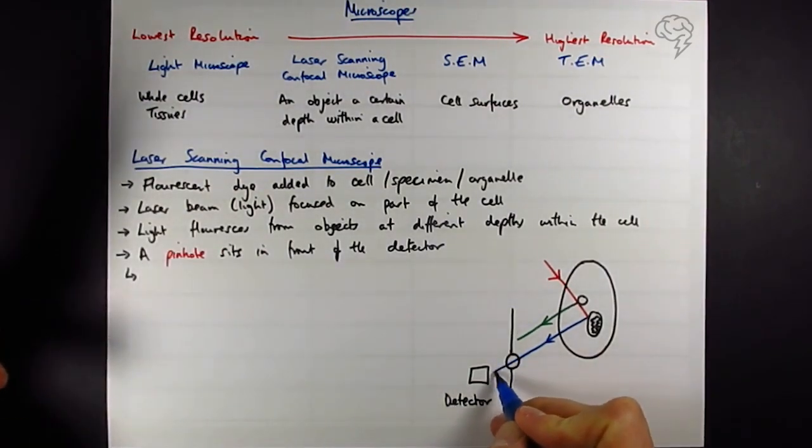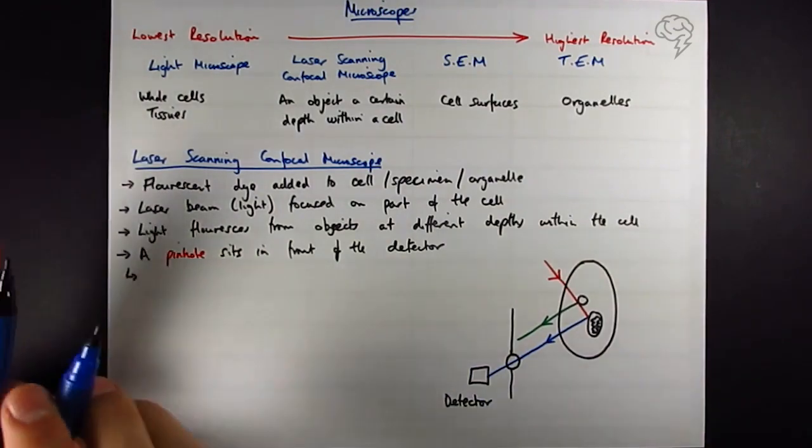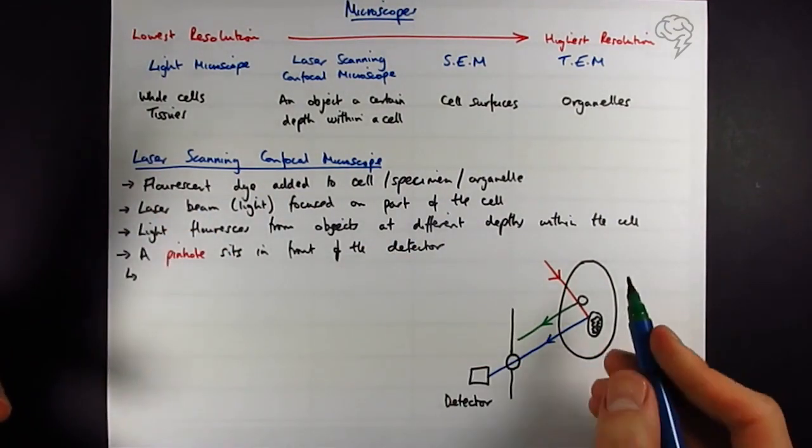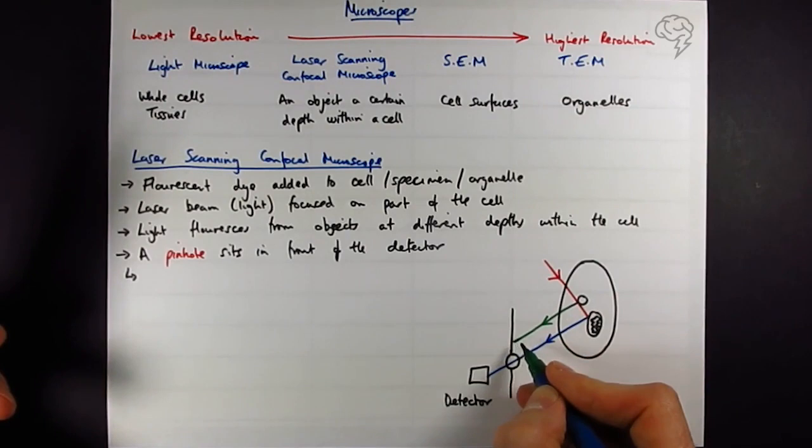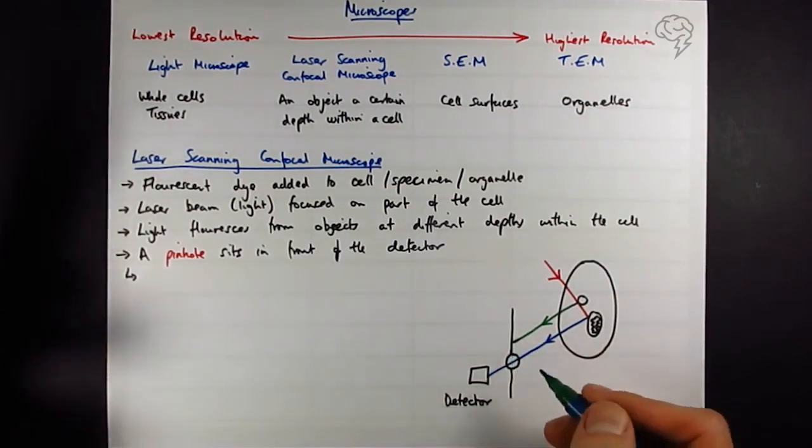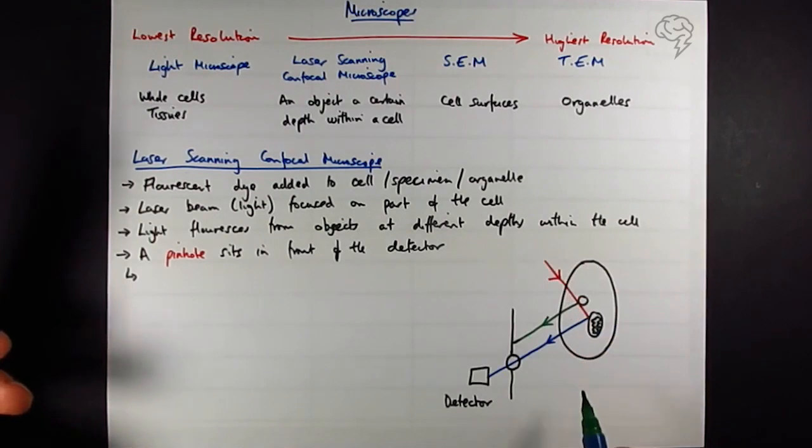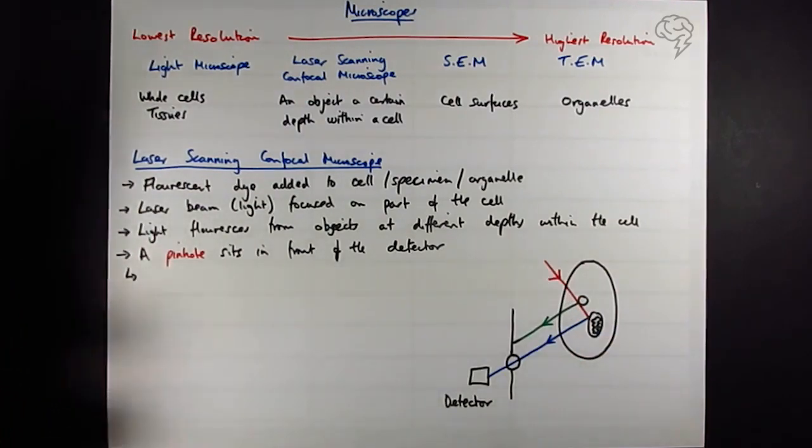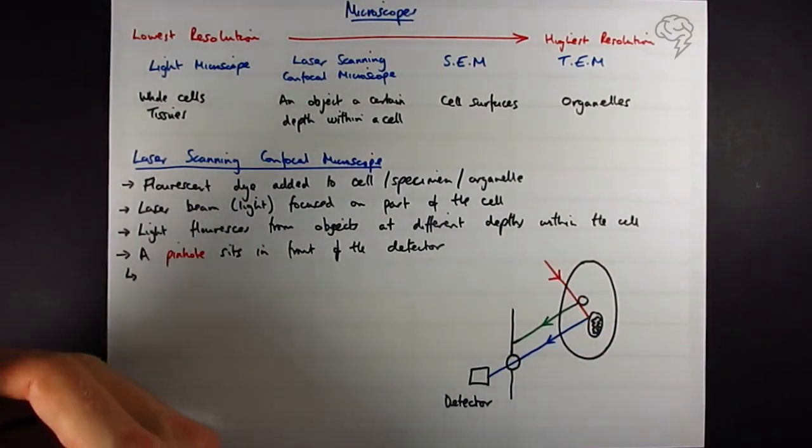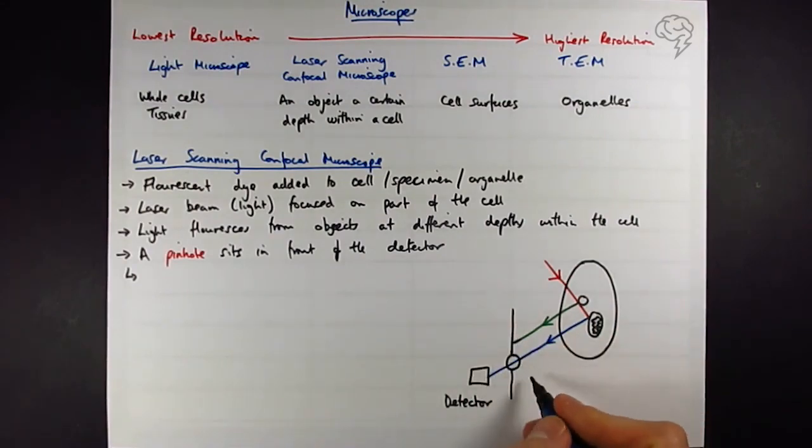And then we have a screen with a pinhole and then my detector is going to sit behind this screen. So this then is going to continue through and hit the detector. But obviously the light that's come from other objects at different depths within the cell are going to hit the screen and they're not going to reach the detector. The position of the detector behind the pinhole is going to determine which bits of light at which depth within the cell are seen. So the pinhole sits in, this is the pinhole.